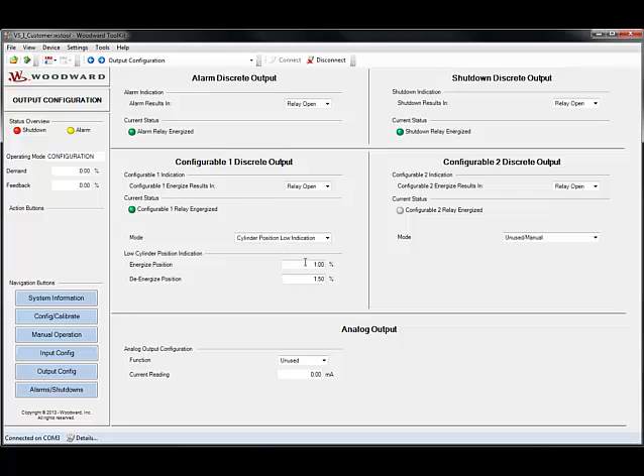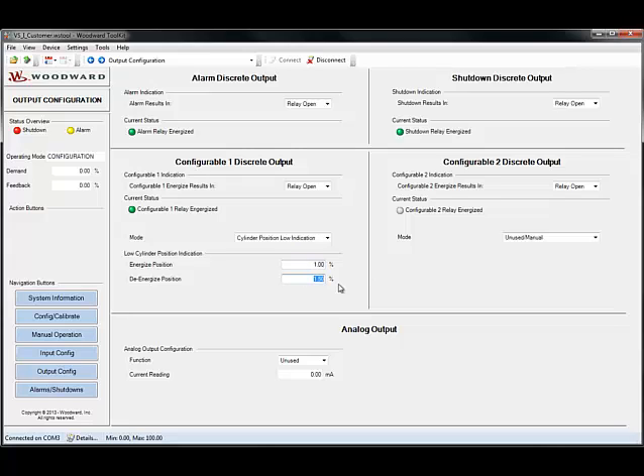This will set when the relay will energize. In this case, it would be when the actuator goes below 1%. And then this is the position at which the relay will de-energize as the actuator comes back through that position, in essence giving the switch some hysteresis.